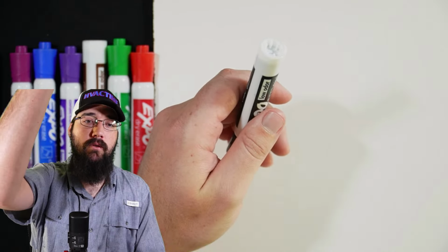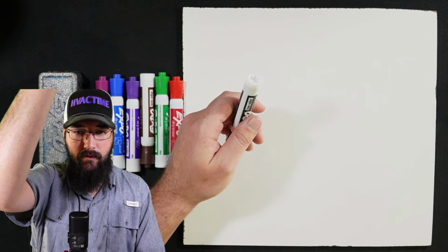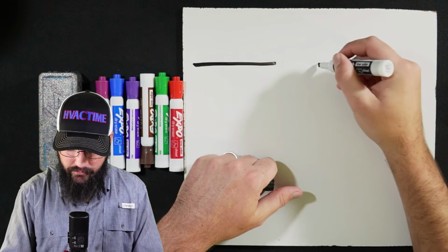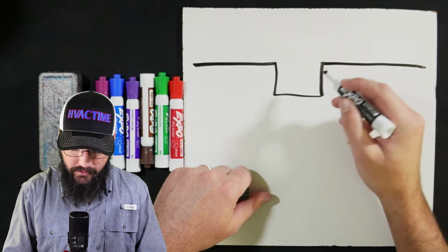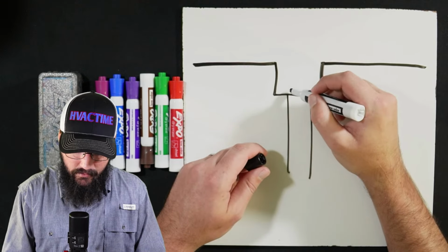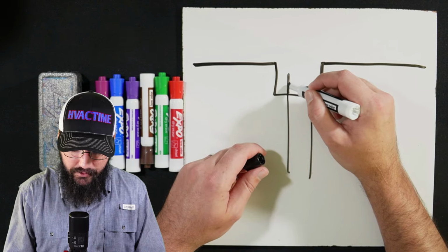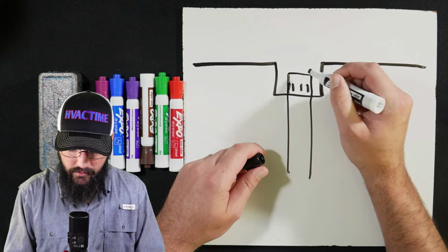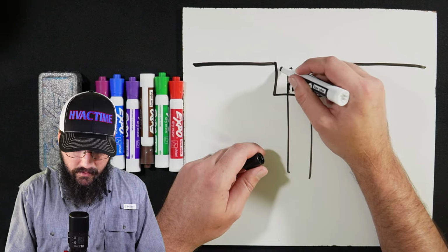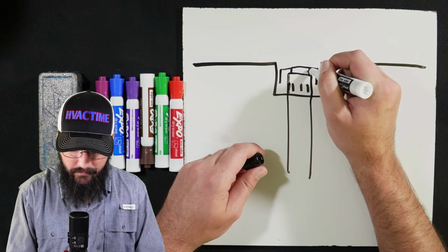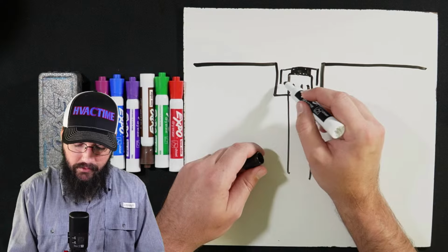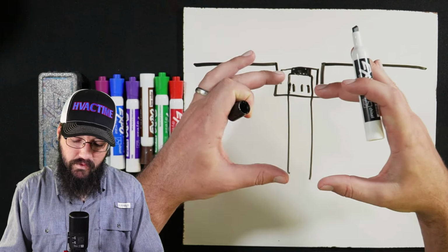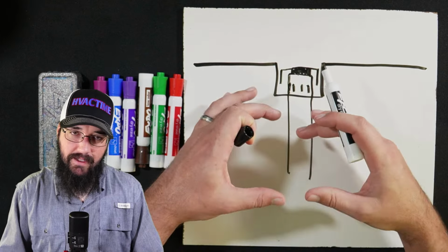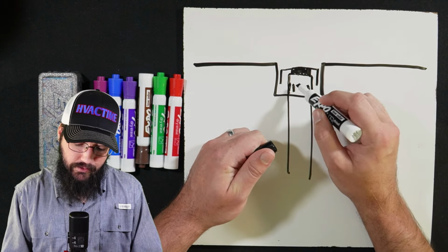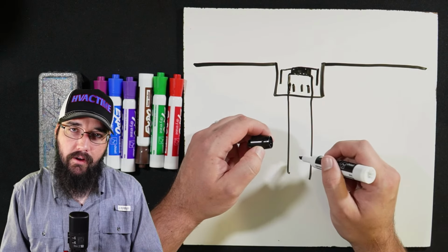Okay, so let's go back over to the whiteboard, into the actual float valve. Let me get my camera. Okay, so coming out of the bottom of the condenser, we have this chamber that dips down, and this is our float valve chamber. So this valve comes up. It's got perforations right here, and there is a float assembly that kind of does this maneuver. So this sits down inside, and this is this kind of bulb sitting on top of the slide mechanism. Okay, this bulb is what is sliding up and down to meter the flow through these slits in the outlet port of the metering valve itself.